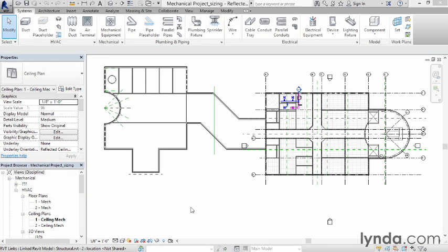To allow Revit to automatically size duct, we must first chop the duct up approximately where we want it to reduce or increase in size based on the calculated airflow going through that specific duct. Once we chop, or I should say split, the duct, we can then run an airflow analysis and allow Revit to size it for us.